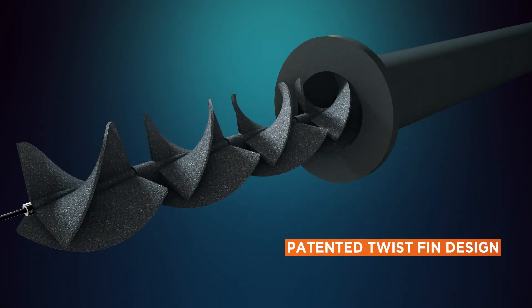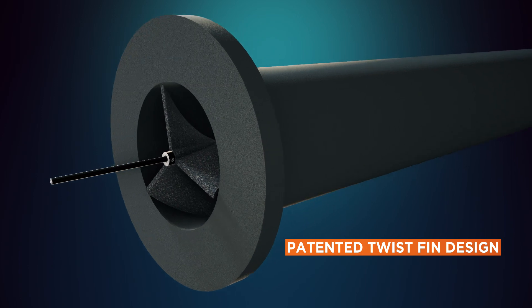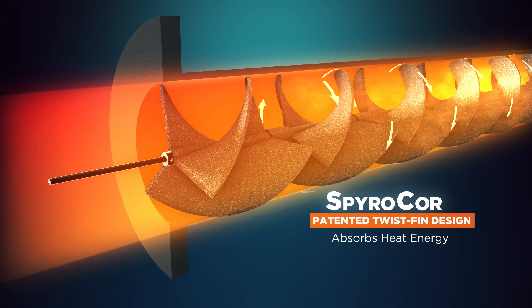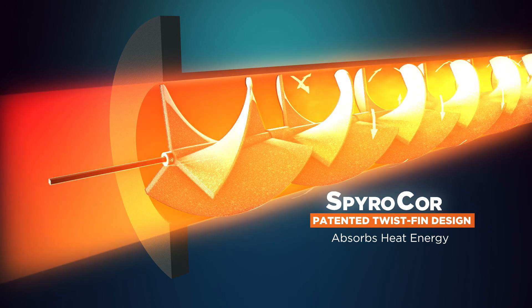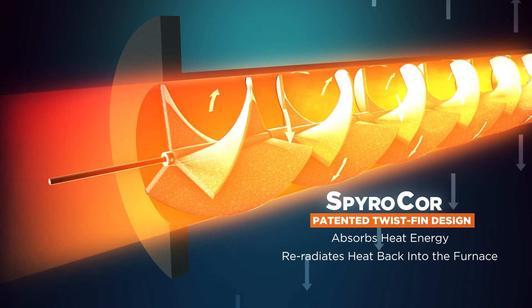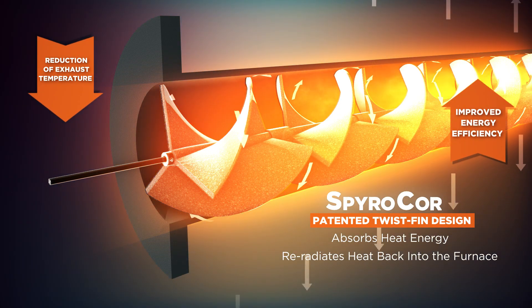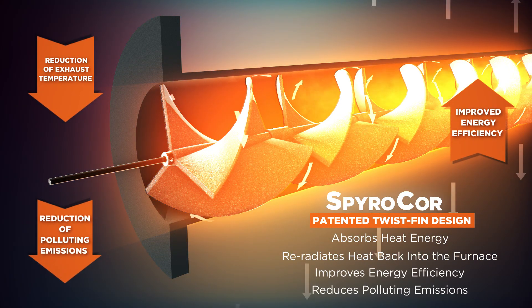The patented twist-fin design is inserted into the exhaust leg of a radiant tube. Once installed, SpyroCor inserts absorb the heat energy from hot exhaust gas that would usually escape and re-radiate the heat back into the furnace. The resulting reduction in exhaust heat temperature improves energy efficiency and reduces polluting emissions.